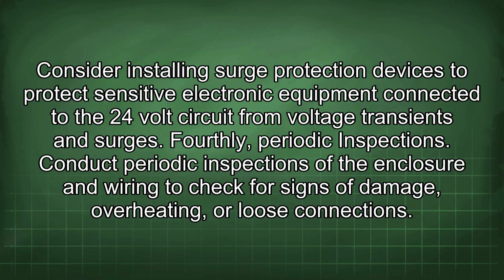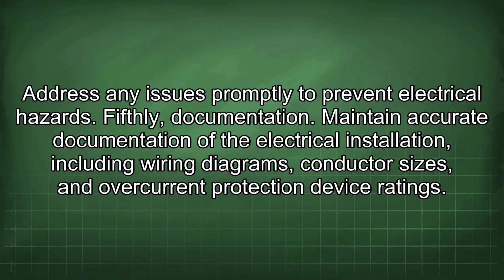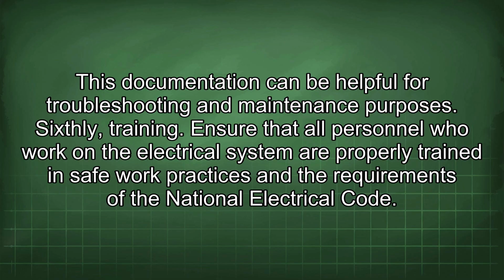transients and surges. Fourthly, periodic inspections. Conduct periodic inspections of the enclosure and wiring to check for signs of damage, overheating, or loose connections. Address any issues promptly to prevent electrical hazards. Fifthly, documentation. Maintain accurate documentation of the electrical installation, including wiring diagrams, conductor sizes, and overcurrent protection device ratings. This documentation can be helpful for troubleshooting and maintenance purposes.